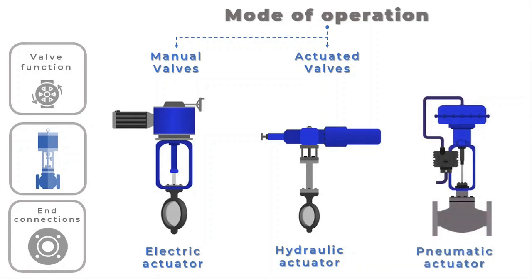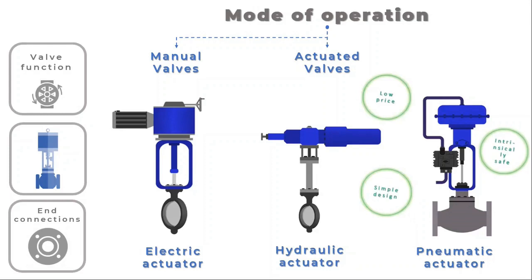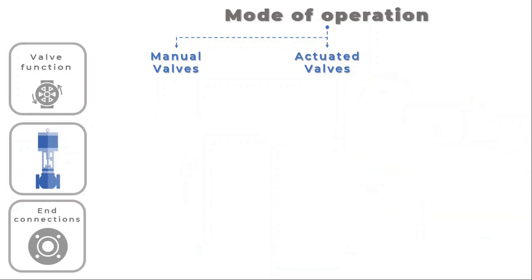Electric motor actuators move the valve stem using a reversible electric motor with a gearing arrangement that enhances torque and slows rotational speed. They were initially intended for on-off applications but some have since been improved for continuous control applications. They are also employed in places where compressed air is not accessible. Hydraulic actuators deliver the force necessary to open a valve using a piston and a pressurized liquid. Actuators that use pneumatics employ air pressure to generate the force necessary to open a valve — they are the most popular types of actuators because of their straightforward construction, reasonable costs, and inherent safety.